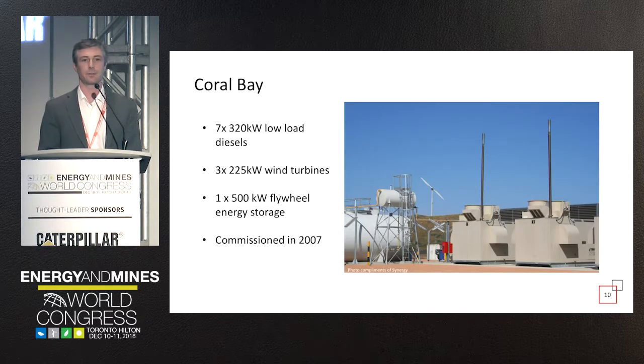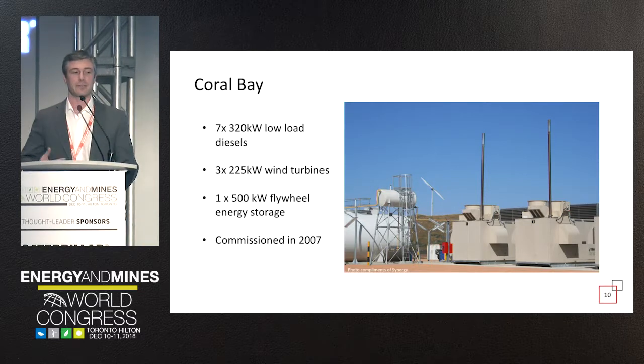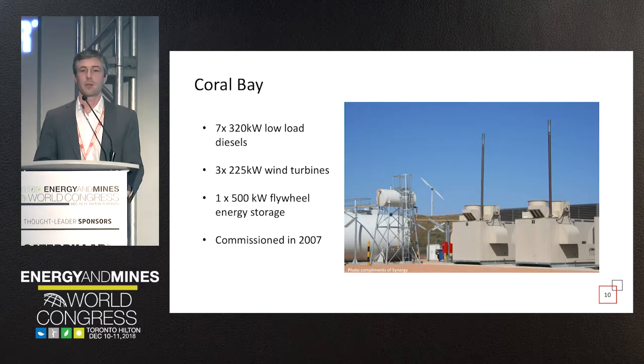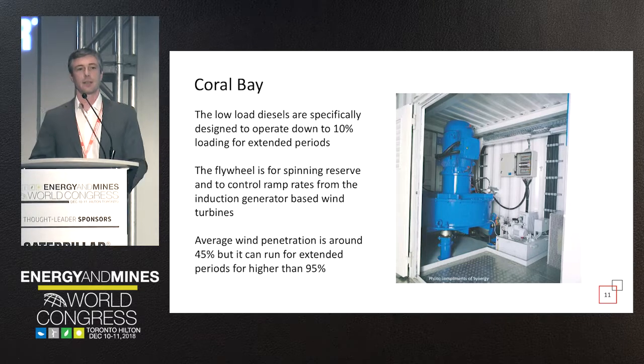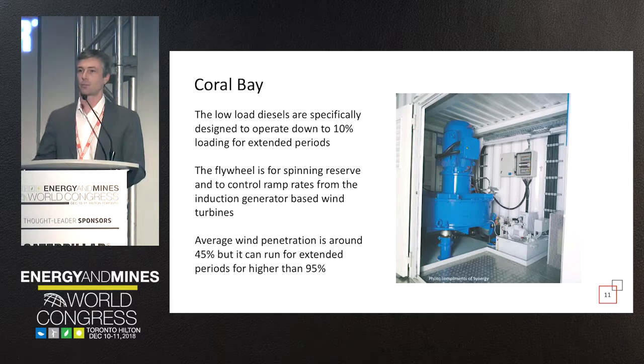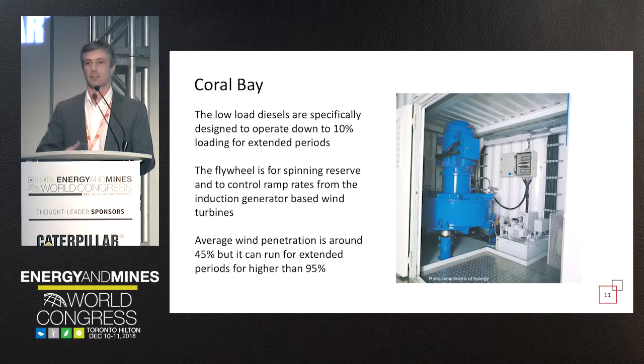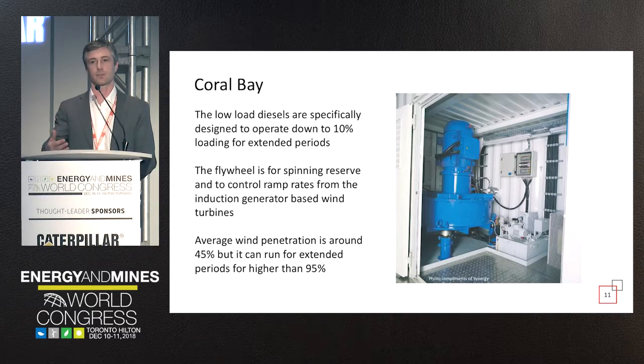Another system we've found useful in very extreme environments: we've talked a lot about the improving economics of lithium-ion batteries, but in extremely cold or extremely hot conditions lithium-ion is not always the best choice. In a system where we've achieved up to 95 percent renewable energy, the solution that fit best was a flywheel. Flywheel technologies have also improved a lot and will continue to improve. There's been less conversation about flywheel energy storage, which is an older technology that has seen significant advancements.